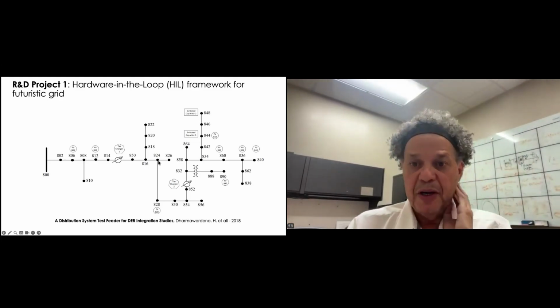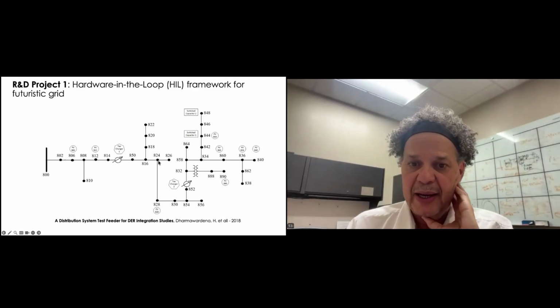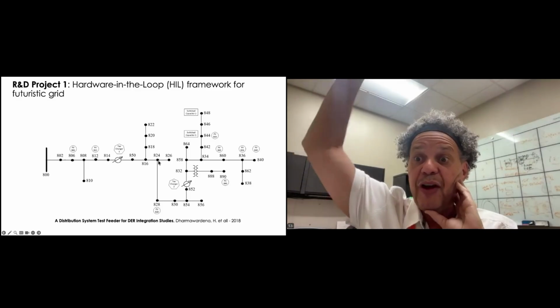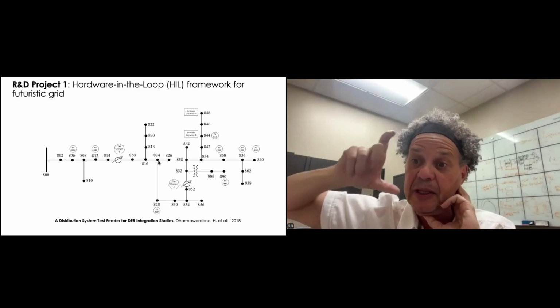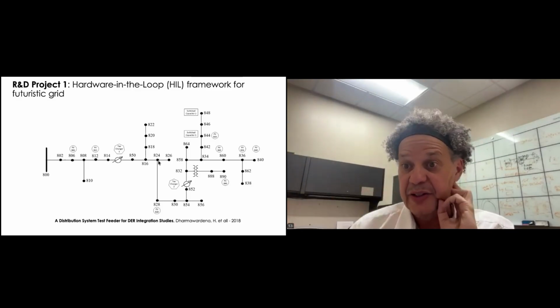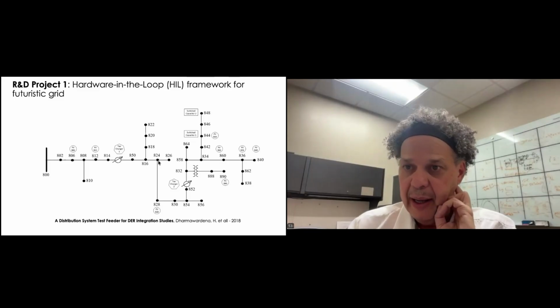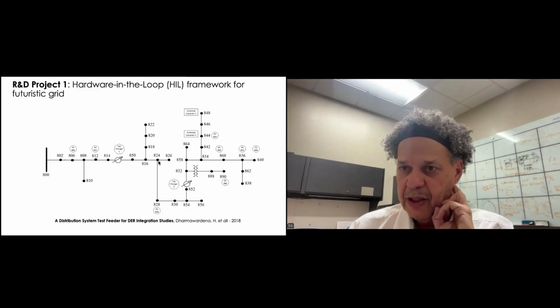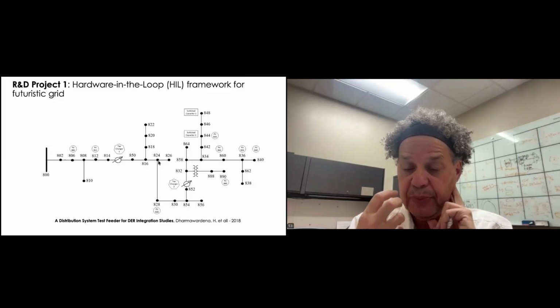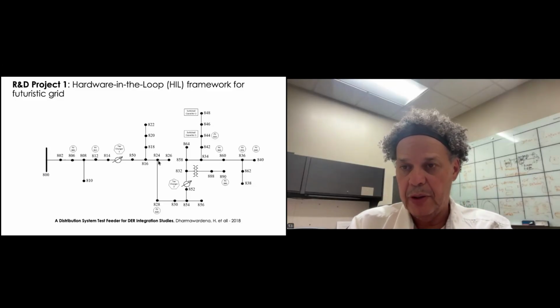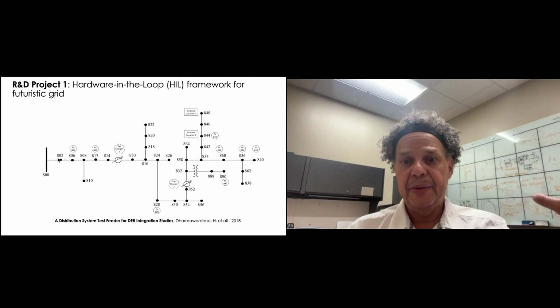Even worse, because you're generating too much power, the voltage goes very high, violating the limits allowed by the standards. You can burn your customers' equipment due to overvoltage, or at a certain point of the day you get undervoltage instead. So now controlling this grid reliably, without causing problems for your customers, is a big deal.